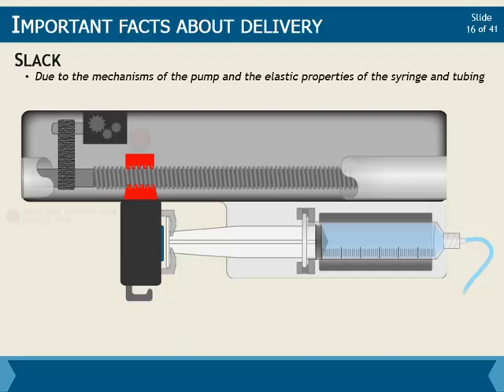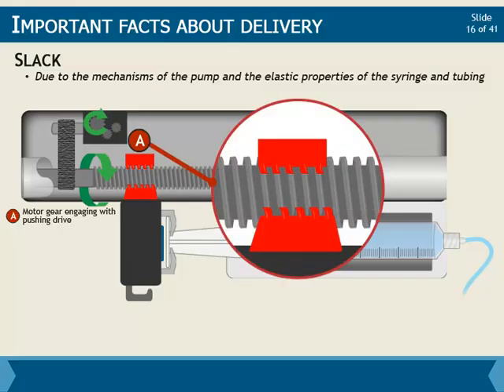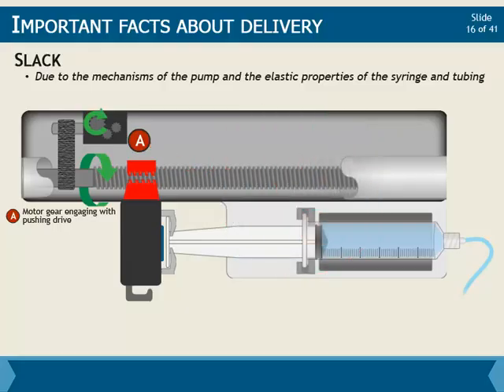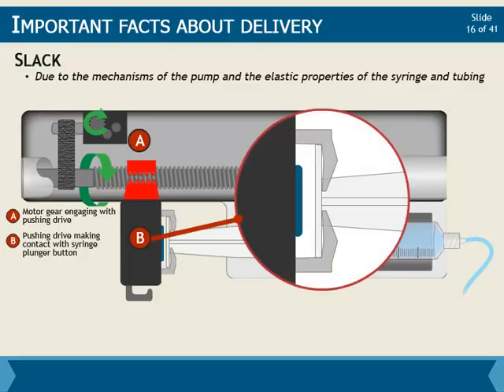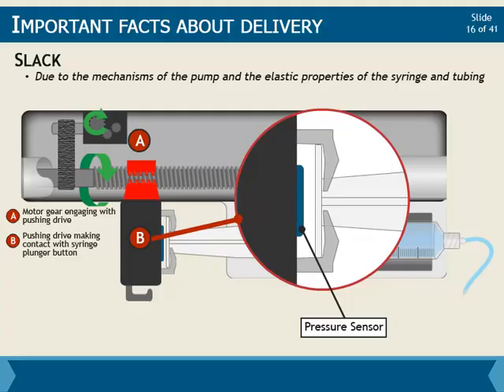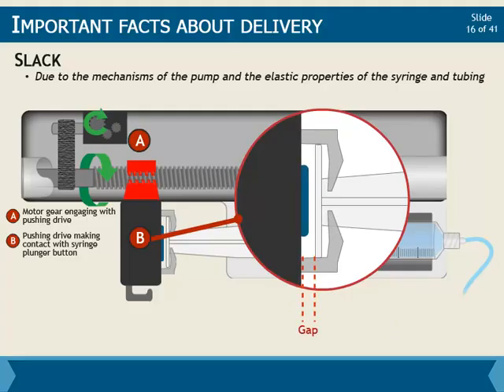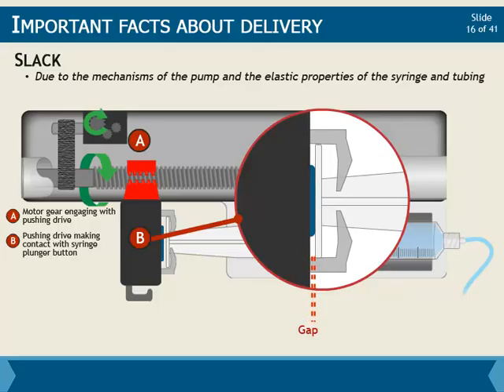These events start with the motor mechanically engaging with the pushing drive, essentially the nut latching onto the threads of the rotating drive shaft. This is followed by the pushing drive moving to make contact with the syringe plunger button. This includes the compression of any mechanisms over the plunger button, such as a pressure sensor. If there is a gap between the plunger button and the pushing drive, there will be a delay as the pump moves to close this gap.